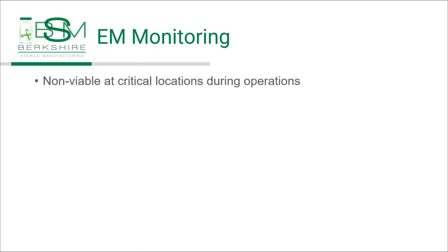Environmental monitoring. Just as in a traditional clean room, environmental monitoring must be performed. Non-viable is performed at critical locations during operations. Viable can be performed periodically near critical locations or continuously.